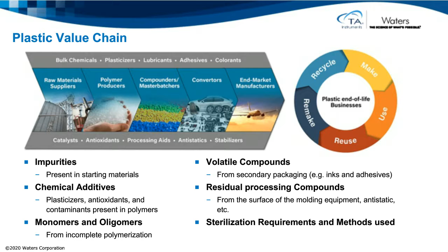As Ben touched upon, there's a range of analytical techniques needed to cover these typical extractables. For example, to identify volatile organic compounds, you would opt for gas chromatography mass spectrometry, maybe using the headspace technique. Electron impact or chemical ionization can be used here. For semi-volatile organic compounds, you would most likely investigate these also with GC-MS, and atmospheric pressure gas chromatography can also be used. For non-volatile organic compounds, and some semi-volatile, liquid chromatography mass spectrometry is the go-to technique, and this can be used with electrospray or atmospheric pressure chemical ionization. For anions, metals and elemental impurities, ion chromatography is needed, or inductively coupled plasma mass spectrometry.